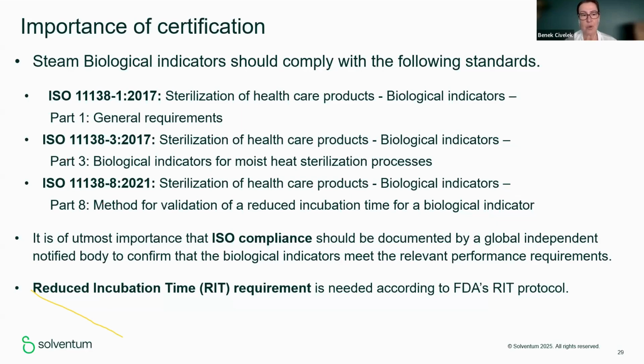But these will not be enough, because we are talking about rapid systems, super rapid systems. So there is a standard which was published in 2021. This is ISO 11138-8. This is the method for validation of a reduced incubation time for a biological indicator. This is important because if you are working with a super rapid system, you have to be able to see the compliance to this standard. This should also be documented by a global independent notified body, and you have to be sure about the performance of this item. And reduced incubation time, in fact, this requirement comes from the FDA protocol, so this ISO standard is also taking its base from this FDA requirement.